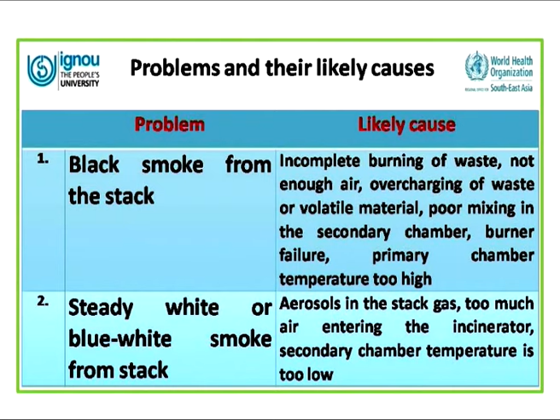Sometimes you may have a steady white or blue-white smoke, and this is because too much air is entering the incinerator, or the temperature in the secondary chamber is too low. Another problem is white smoke or white haze appearing a short distance from the stack, which is because hydrochloric acid is getting condensed.